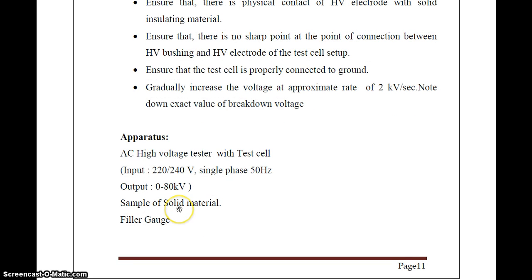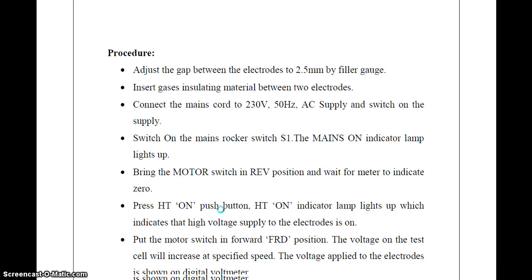That is an AC high voltage tester with test cell, that is the sphere pair test cell. Input is 220 volt to 240 volt, single phase 50 Hz. Output is 80 kilovolt. Then a sample of solid material, the sphere electrode, and gaseous insulating material like air is used.